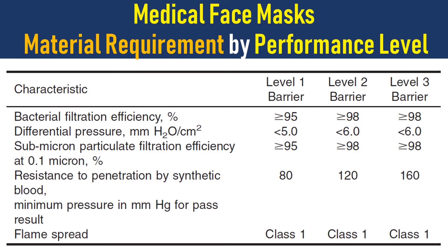Medical face mask material requirements by performance level. For different performance levels the requirements are different. For bacterial filtration efficiency, level one barrier requires not less than 95 percent. For level two it should be equal to or greater than 98 percent, and for level three protection it should also be equal to or greater than 98 percent.